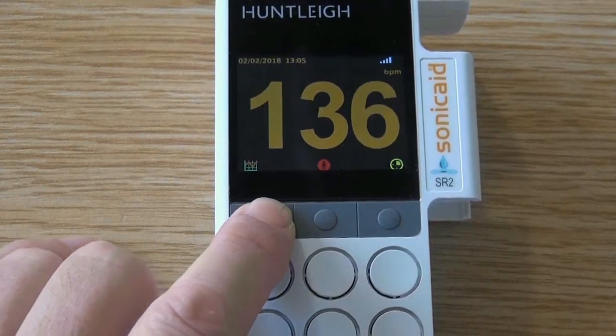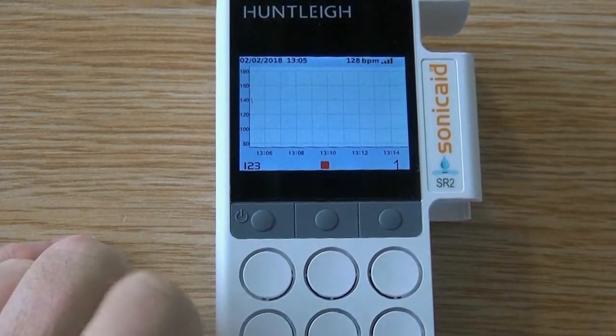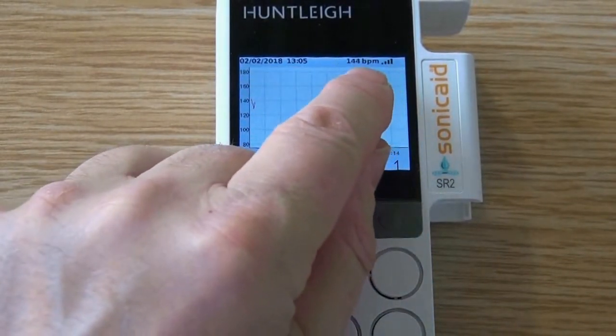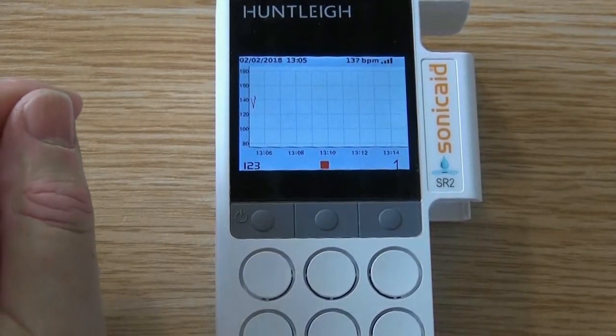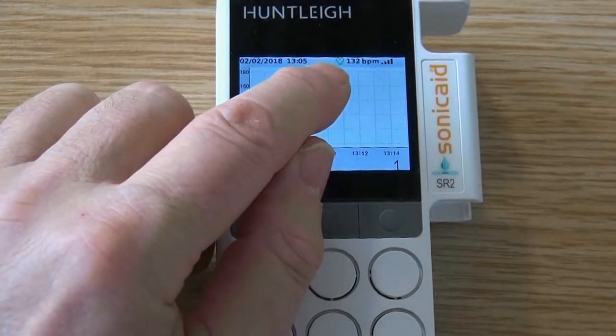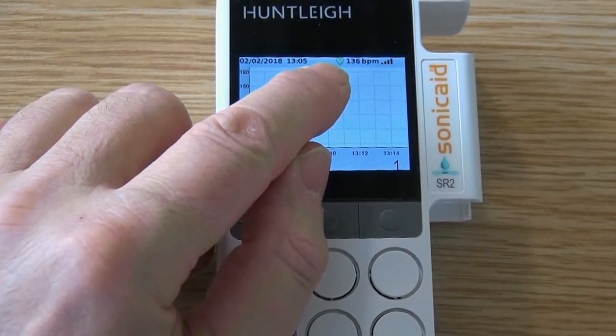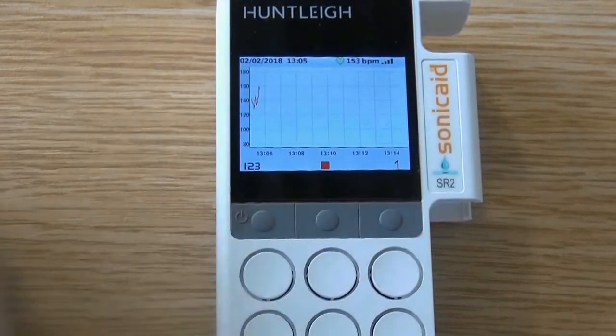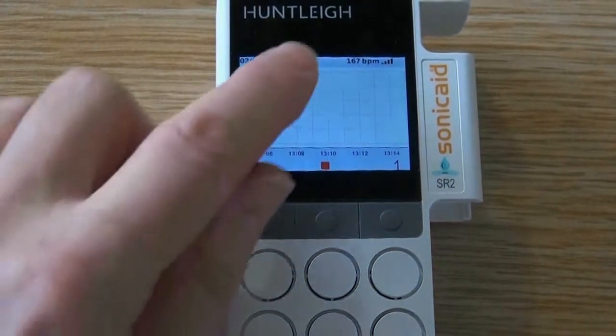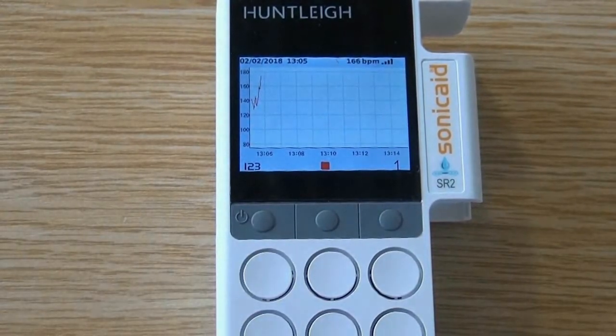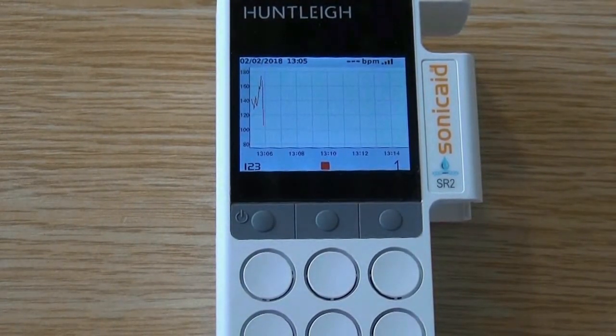In big numbers mode, click the left button to enter trace view. In this view, you can see the date and time, pulse indicator, heart rate and signal quality indicator. The flashing heart rate symbol changes color to red if the high or low rate threshold is reached, and changes back to green once it returns to within the set range. This current trace view is set to 1 centimeter a minute.